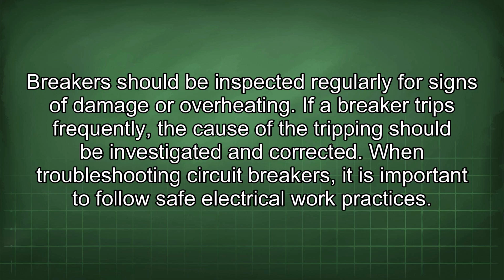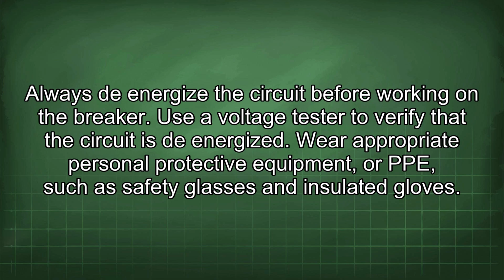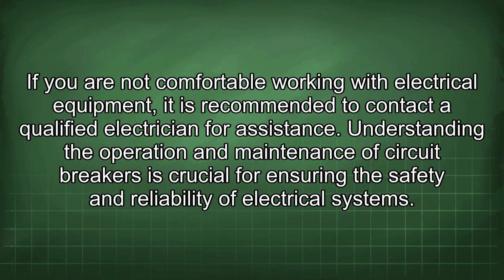When troubleshooting circuit breakers, it is important to follow safe electrical work practices. Always de-energize the circuit before working on the breaker. Use a voltage tester to verify that the circuit is de-energized. Wear appropriate personal protective equipment, or PPE, such as safety glasses and insulated gloves. If you are not comfortable working with electrical equipment, it is recommended to contact a qualified electrician for assistance.